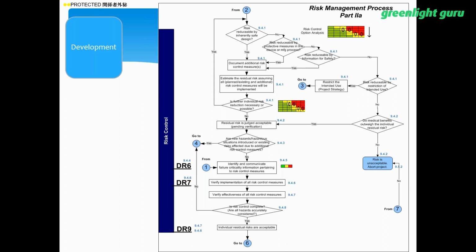If, however, during your testing, during design verification, design validation, characterization testing, which I love to death, those tests come up and say, hey, marketing, you decided we wanted to go with a design life of 4 years and service for 2. However, my characterization testing indicates we can only go to 3 years to meet all of our safety margins. Then you may decide marketing wants 4, technically I can do 3. We're going to define design life as 3 years plus 2 years service.